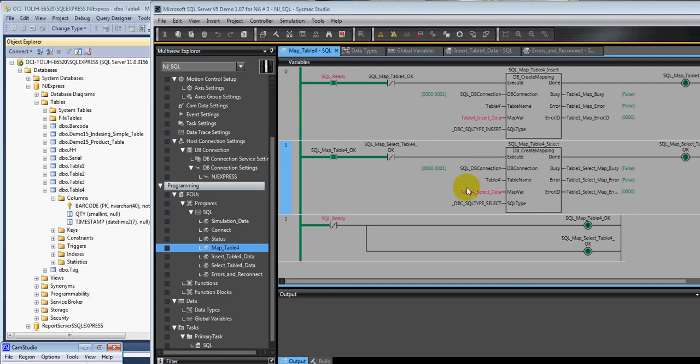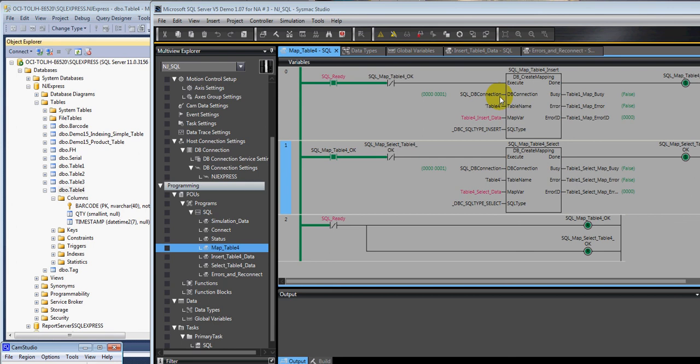The next thing you need to know is you're only allowed to execute the create mapping 60 times. And a create mapping, like the other network type instructions, can take longer than one scan to execute. And you're only allowed to execute 32 network type instructions on any given scan.